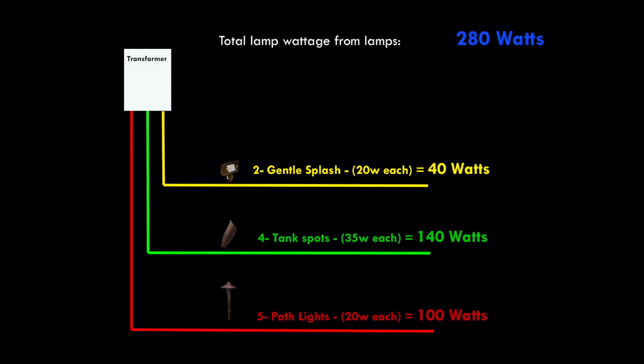At the top of the page, we have totaled up all of our lamp wattage, which comes to 280 watts. Now this is where the 80% rule becomes of paramount importance, because most folks and even many contractors would see 280 watts and mistakenly settle on a 300-watt transformer. Since their total watts are under the 300-watt rated capacity of the transformer, they falsely assume that they are good to go. What most folks fail to do next is multiply the total watts times 1.2.